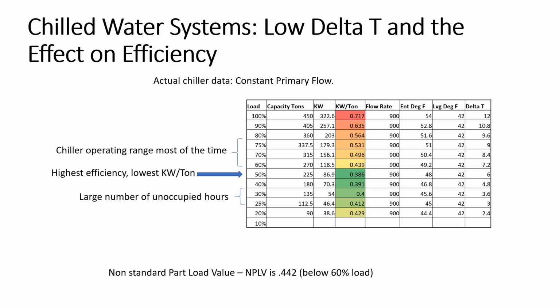So if you had this data when you were designing the system or coming up with a solution, this is where you'd look at the most efficient point at 70%. I would rather have its best efficiency at 70% because that's where I'm going to be running most of the time. Either that or break up the load into different size machines that run most efficient for longer hours. This is one machine, and so it's the only machine that they run, and it has to cover this capacity high to low. In this case, it gets down to 90 tons, but I don't think I want to run at 90 tons for a long time. And I certainly don't want to run at 80%, 360 tons for a long time, because the efficiency goes down as I increase my load.